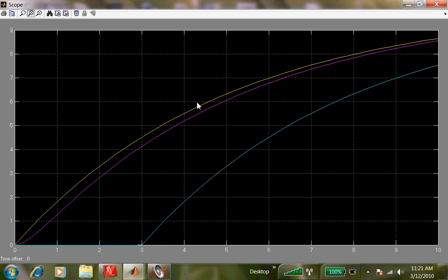Okay. So the process temperature output is related to the inlet temperature. What is happening is the inlet temperature is changing by 10 degrees. And the question is, how does the outlet temperature of the process tank change? It changes according to the yellow line. That's the first order process. Okay. First order transfer function. Then we are dipping now the thermocouple and saying, what is coming out of the thermocouple? That is the purple line. Because the thermocouple doesn't instantaneously read the temperature coming out. There is a lag. That lag is not a pure transportation lag. It's a lag because of the dynamic response of the thermocouple itself. It needs to heat up the elements. Okay.